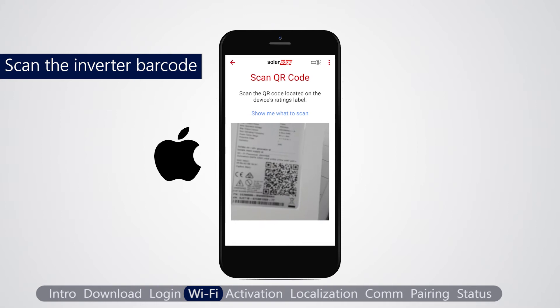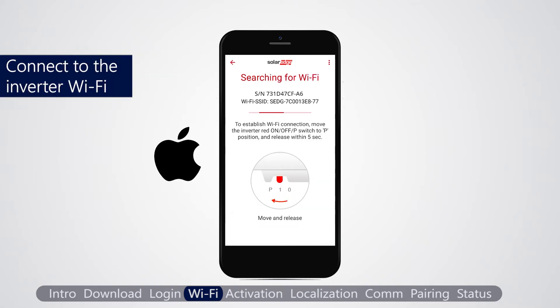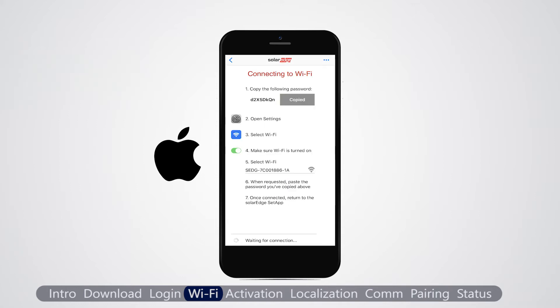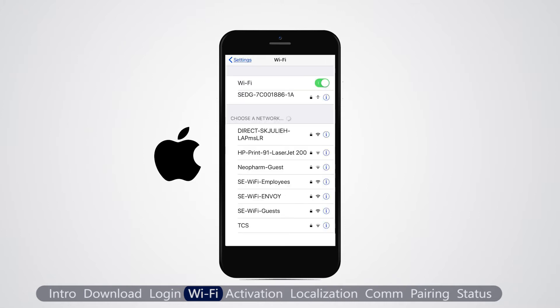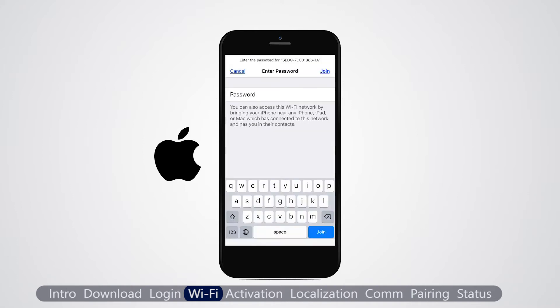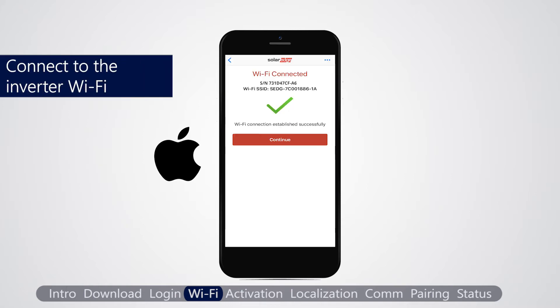Scan the inverter barcode. Move the on/off/P switch to P and release within 5 seconds. Tap copy to store the Wi-Fi password. In the Wi-Fi settings screen, make sure Wi-Fi is on and choose the network name that corresponds to the inverter serial number. Paste the password and tap join. Setup creates a Wi-Fi connection.